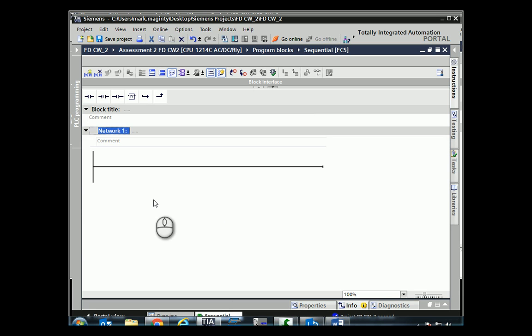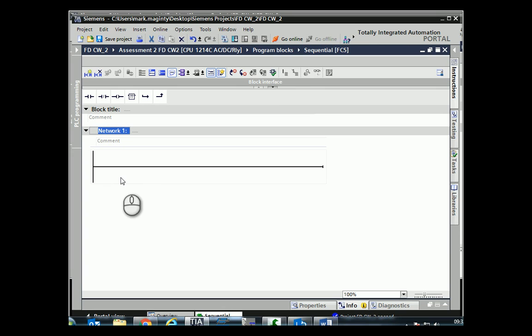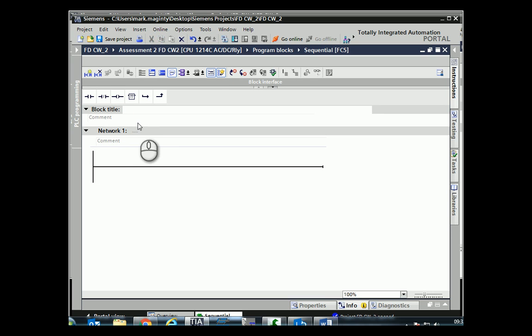This is a video showing how to do sequential programming via ladder logic. What we have on screen is a method of developing a sequential program from what is usually only ever deemed to be a scan-type program. We first need to figure out our sequence. I'll pick a random example: A+, then B+, then B- immediately after, then A-. That's two double-acting cylinders controlled by two double-solenoid valves, with a start button and a stop button — a very basic electro-pneumatic sequence controlled via PLC software in a sequential manner.